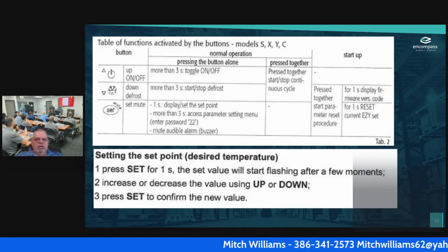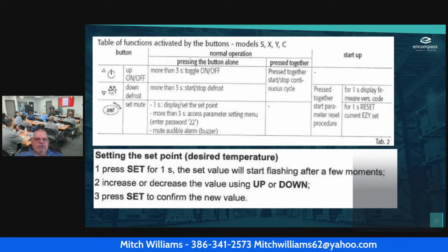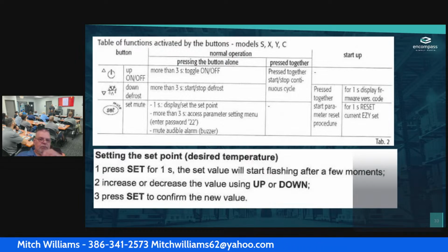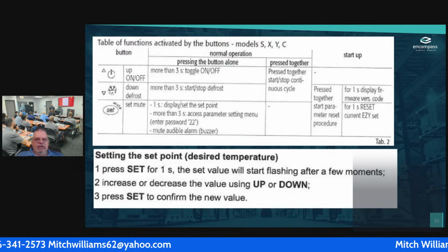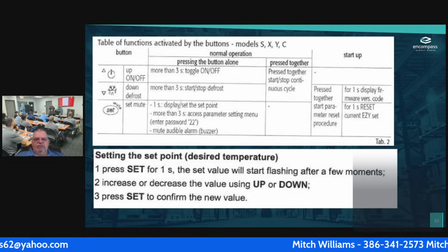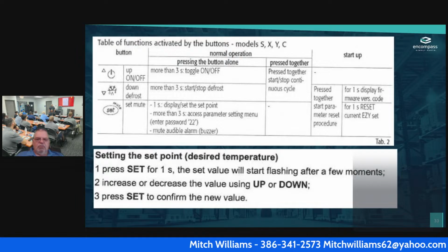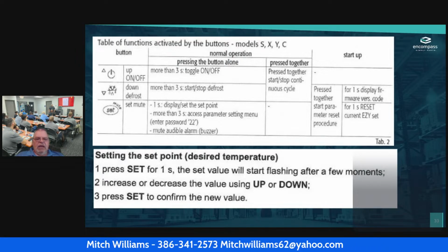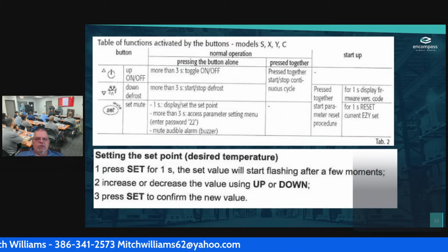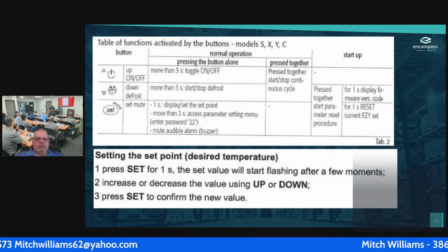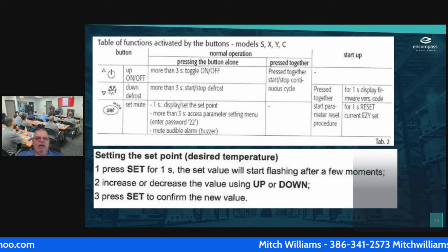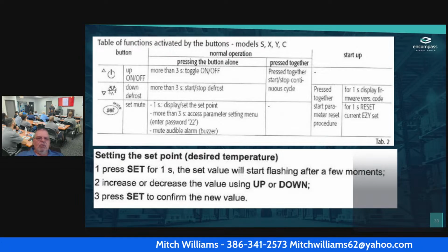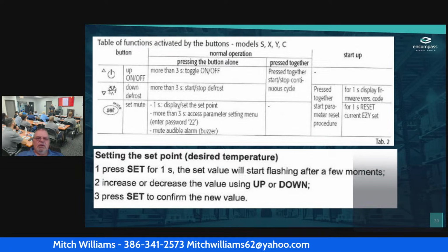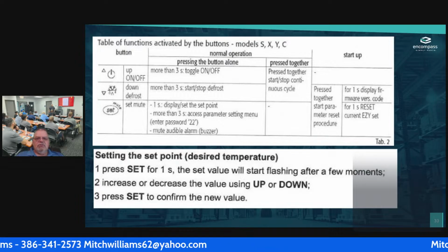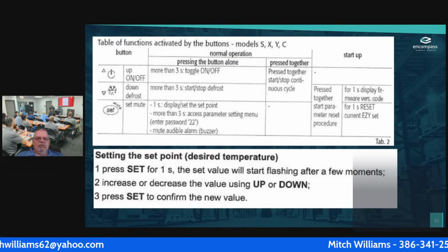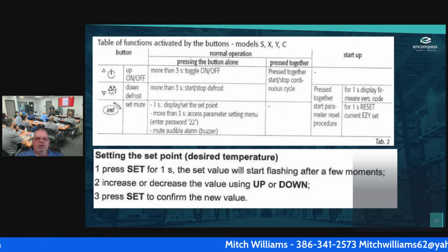So setting the desired set point, okay, the desired temperature. Press set for 1 second. The set value will start flashing after a few moments. Then after that, I'm going to increase or decrease the value using the up or down button, and then I'm going to press confirm for the new value. Okay. So this right here, if you look right here, this is the on off. More than 3 seconds to toggle it on off. The down defrost is 3 seconds.